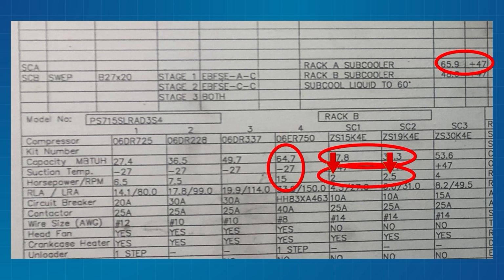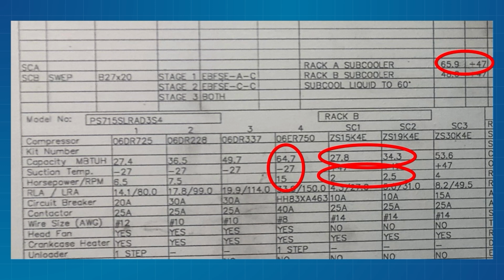2 horse or 4.5. Holy, you get the same compressor capacity for a third of the horsepower. There it is. So if I turn off my subcooler, I need another one of these at 15 horse. Or I can turn on my subcooler and do it with 4.5 horse. That's significant, right? That's not a small amount.